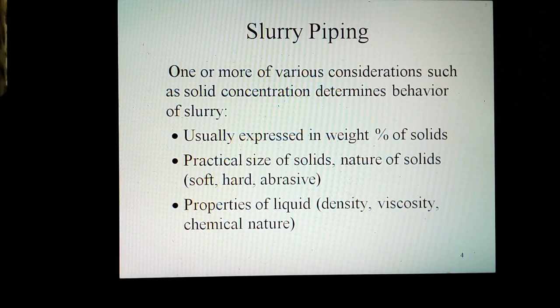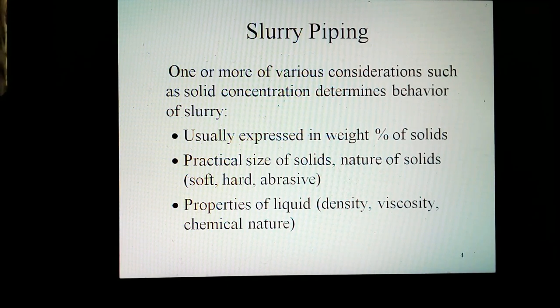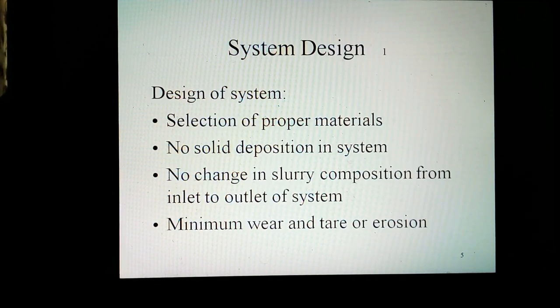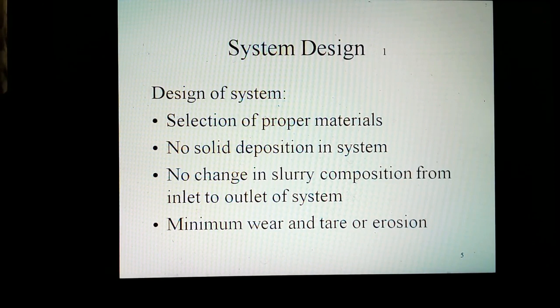One or more of various considerations determines the behavior of slurry. Solid concentration, usually expressed in weight percent of solid; particle size of solid; nature of solid — soft, hard, abrasive; and properties of liquid — density, viscosity, and chemical nature. The design of the system, including selection of proper materials, is governed by the following general considerations: no solid deposition in the system, no change in slurry composition from inlet to outlet, and minimum wear, tear, or erosion.